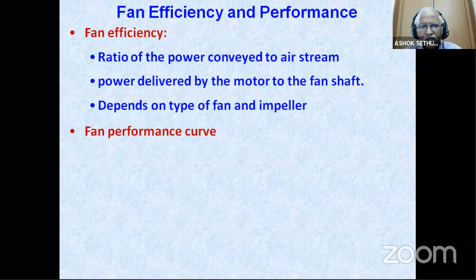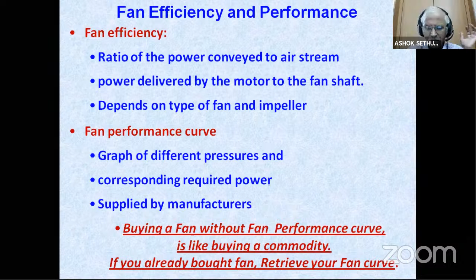So the fan efficiency and the performance is more important, especially what is delivered at the motor, what is delivered at the fan shaft, and what is the type of impeller. The industry is buying fans as a commodity. They should not buy the fan like a commodity. They should buy the fan with all the technical specs. When you go for industrial visits, you go to the industry and you ask for the blower spec. You learn more about the blower. Blowers are going to give a lot of energy savings to the given industry.